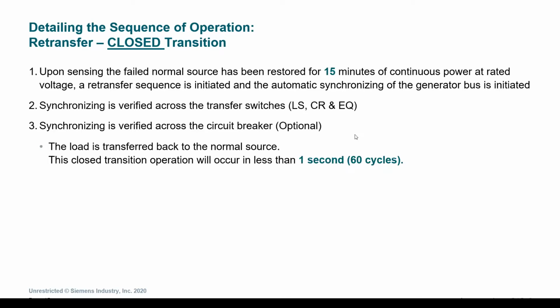Many of you know that NFPA 99 requires transfer switches for the life safety, critical, and equipment branch, and that the optional standby branch can actually be done utilizing circuit breaker interlocks. In this example, the optional standby is being done with circuit breakers, in which case the load is transferred back to the normal source, and that synchronizing is verified across the circuit breaker. It's important to identify that the closed transition operation in this example will occur in less than a second or 60 cycles. This, again, is something that needs to be verified by the utility company and ranges based off of each of their specific design requirements and parameters.